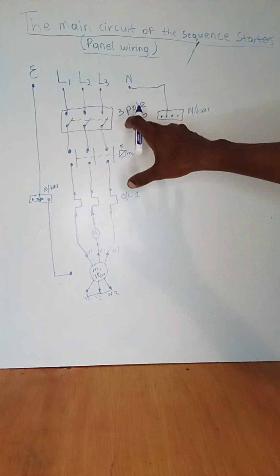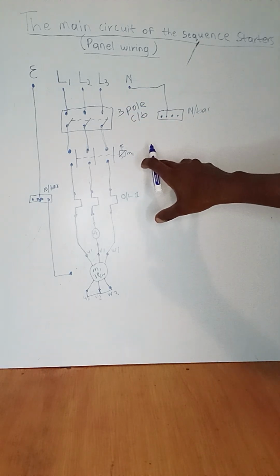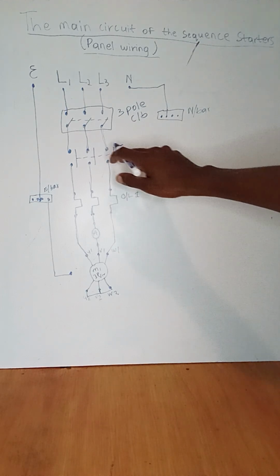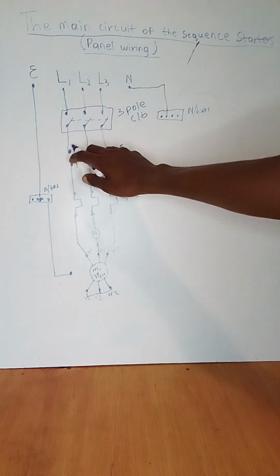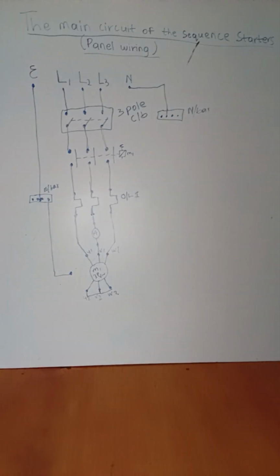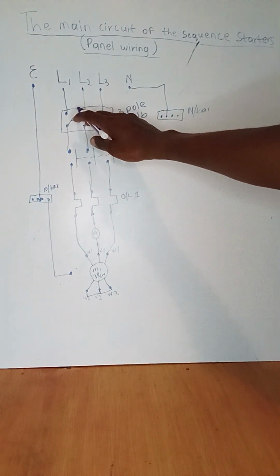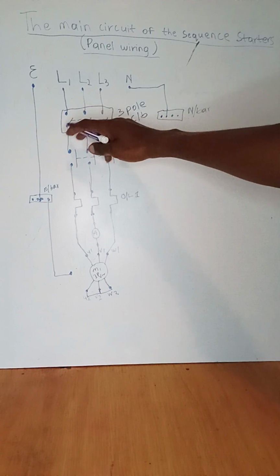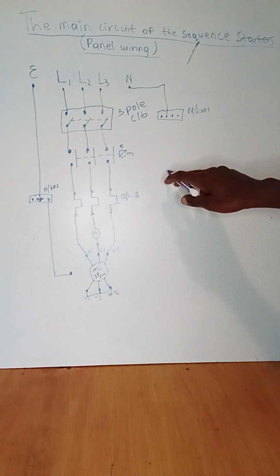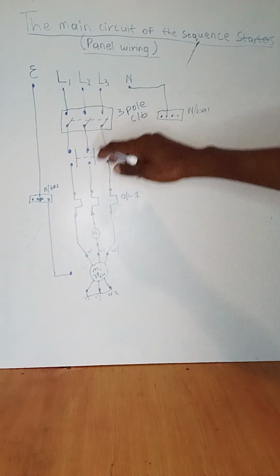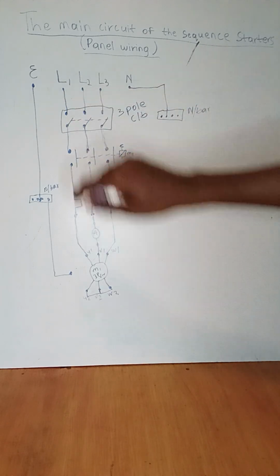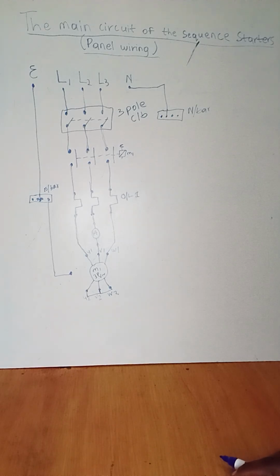So if they will both use the triple circuit breaker, we must supply the connection of motor 2 by branching the supply under the triple circuit breaker, because if we are branching the supply above the triple circuit breaker, it means motor 2 will not depend on the triple circuit breaker, but will depend on the supply voltage, which will be wrong.